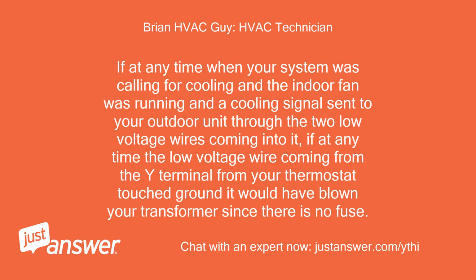If at any time when your system was calling for cooling and the indoor fan was running and a cooling signal sent to your outdoor unit through the two low voltage wires coming into it, if at any time the low voltage wire coming from the Y terminal from your thermostat touched ground, it would have blown your transformer since there is no fuse.